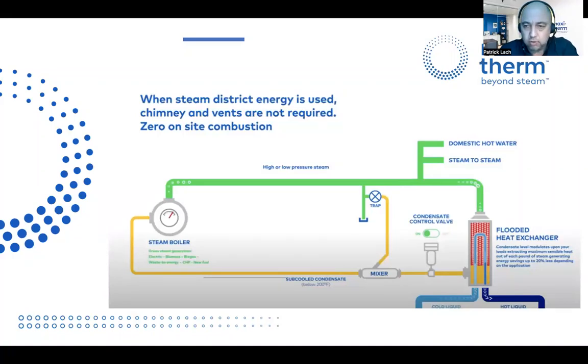I think over 1,200 customers are tied to the steam distribution system. If I remember correctly, the steam pressure coming into the building is 175 PSI, around that. All of them are reducing the steam pressure to 10, and then they're dumping condensate to drain. To dump the condensate to drain, they need to cool it down to 140, injecting fresh water all the time, which you are invoiced for that use of fresh water.